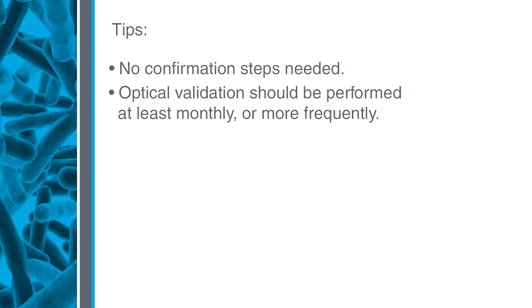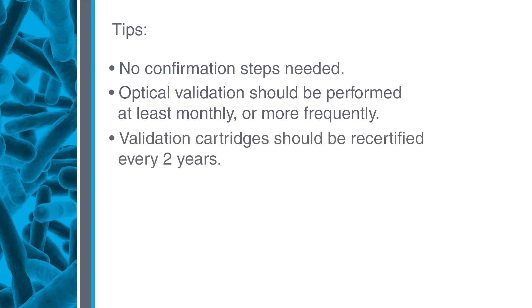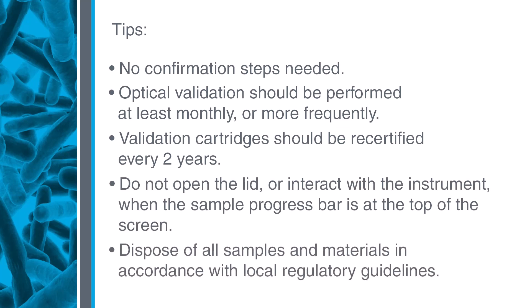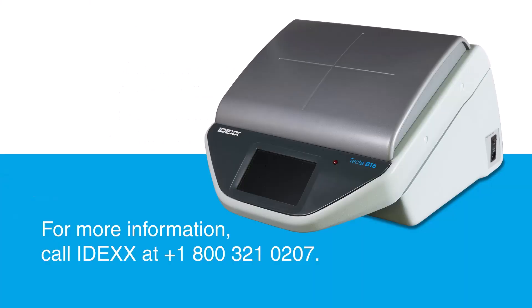Optical validation should be performed at least monthly, or more frequently for daily users. Validation cartridges should be recertified every two years. Do not open the lid when the sample progress bar is showing at the top of the screen. Dispose of all samples and materials in accordance with local regulatory guidelines. If you have questions or need more information, call the IDEXX water microbiology experts at the number on your screen.